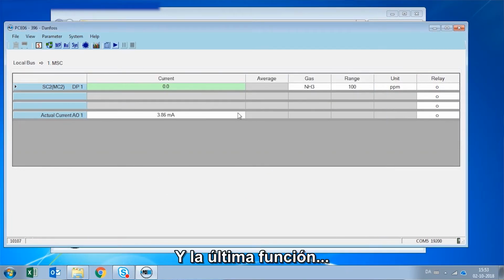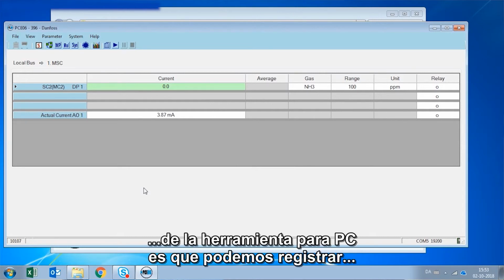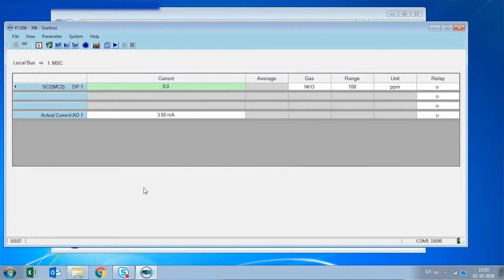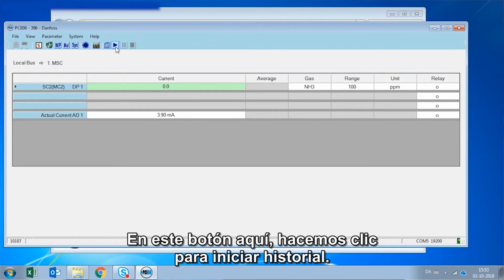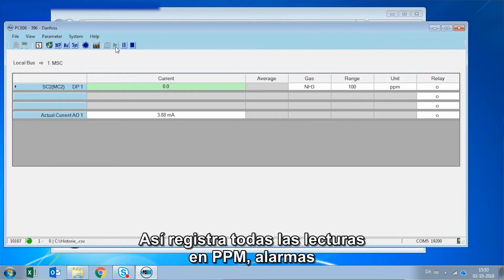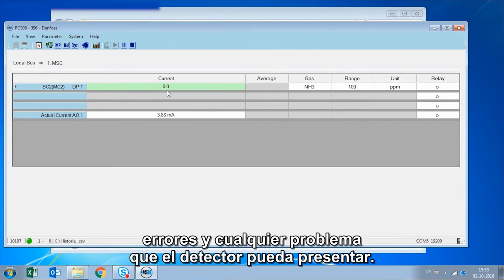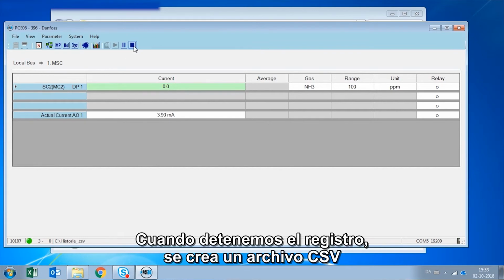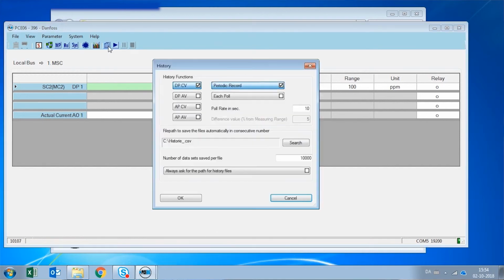And the final feature of the PC tool is that we can record the readings of this gas detector. So on this button here, if we click Start History, now it is recording all readings in ppms, alarms, errors, and any issue that the gas detector might present. And when we stop this recording, it's going to create a CSV file where we can see all these values.